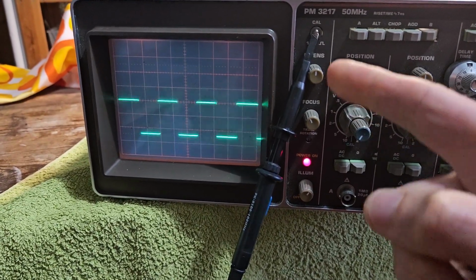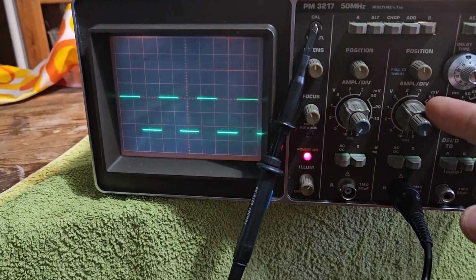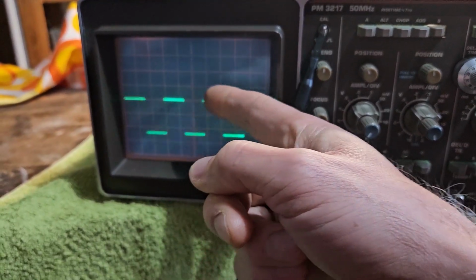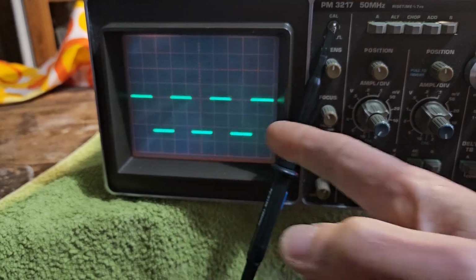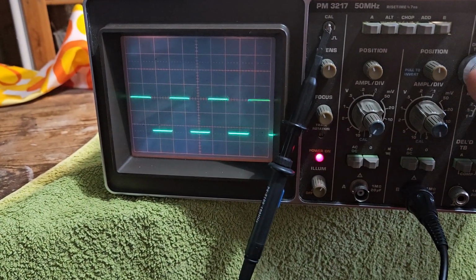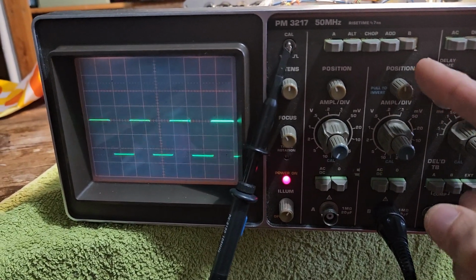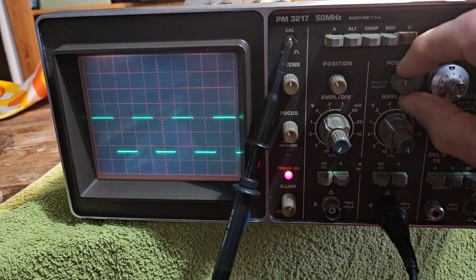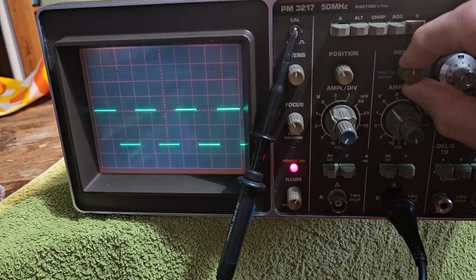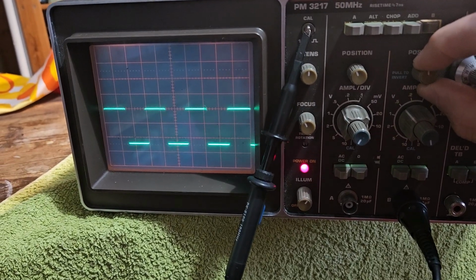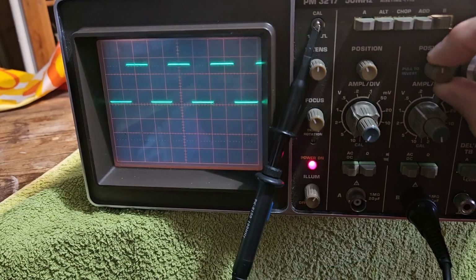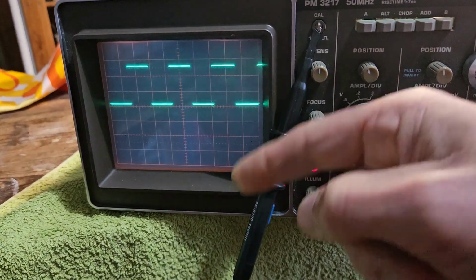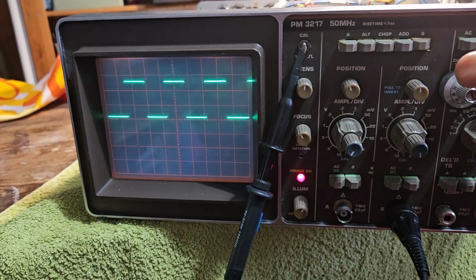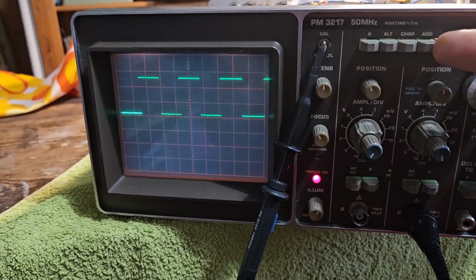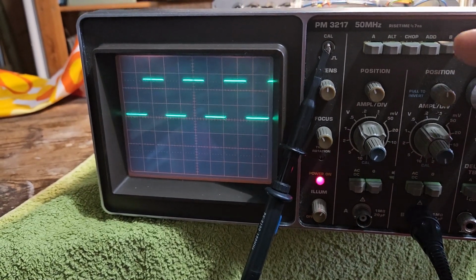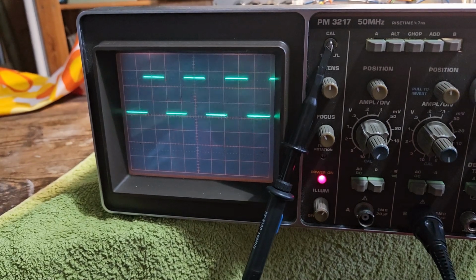So looking at this trace again through the B amplifier, you can see it actually goes from ground down to negative, interestingly. I hadn't noticed that before. But anyway, you've got on the B channel this extra function on the position knob, which I'll make sure that top is ground, and then if you pull it out it inverts. So now everything that was negative is positive. Okay, so that is useful because you've got a function to add A and B here, and so you can basically do a negation if you've inverted one of the channels.